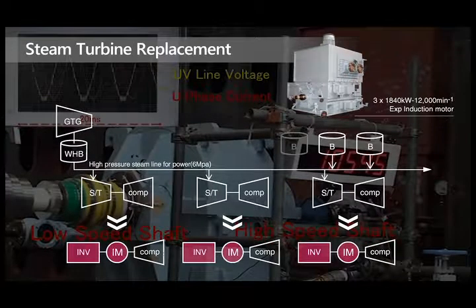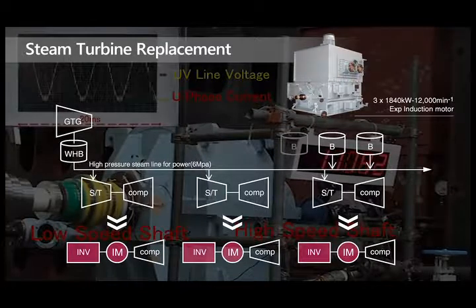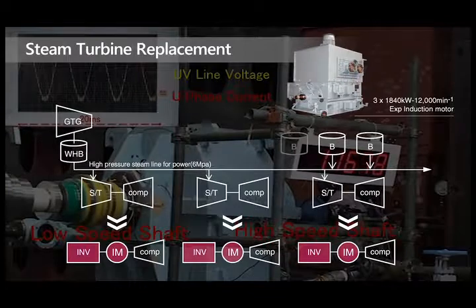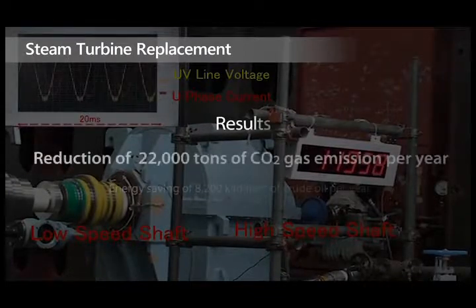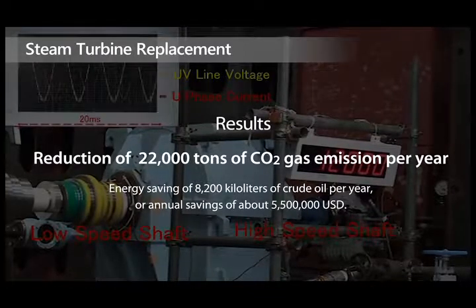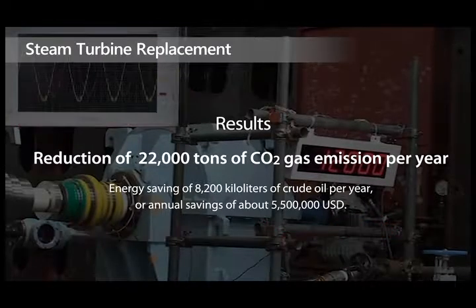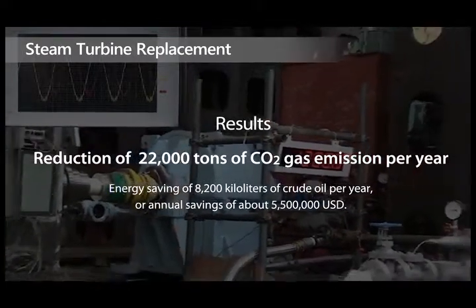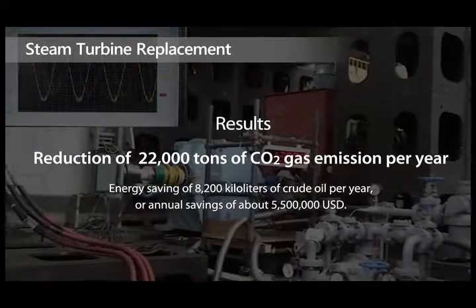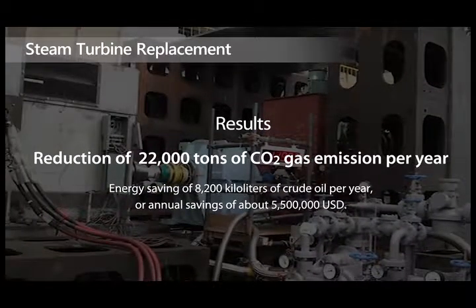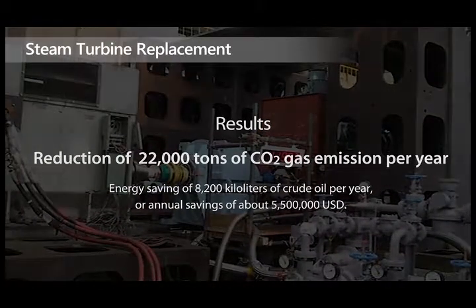3 steam turbines were replaced with 3 1,840 kilowatt induction motors. The motor speed was 12,000 rotations per minute. This CO2 gas emission reduction was brought about by less boiler fuel used in the refinery. So, the change to an electric motor was instrumental in reduction in both crude oil consumption and CO2 gas emission.